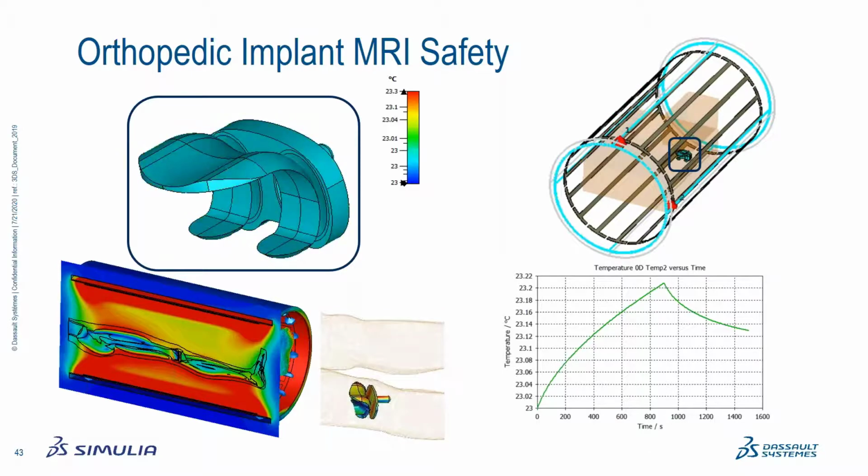When the same procedure is repeated with a detailed human body model at the knee joint, the electrical field distribution is quite different on the implant. For this reason, the FDA has more recently provided guidelines to use human simulation models, wherein the implants can be certified for safety if they meet the limits with those virtual human models.